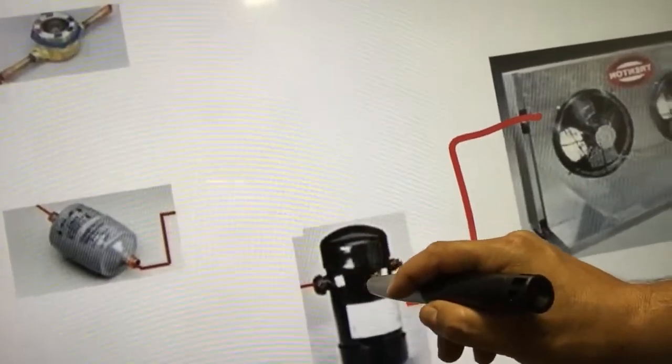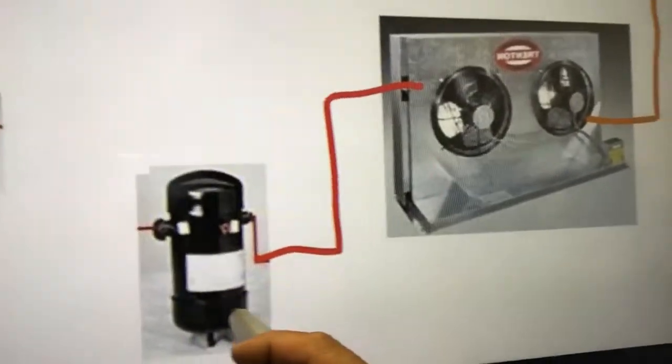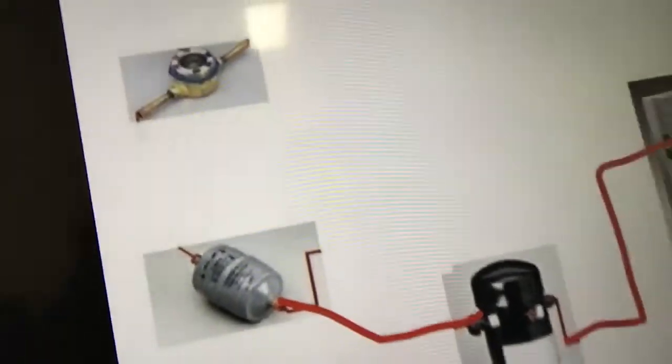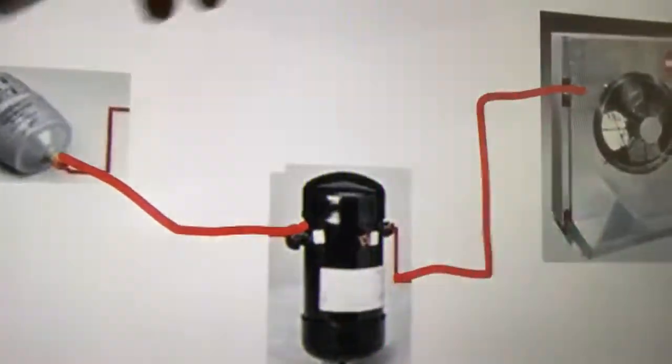From the receiver tank, notice that the refrigerant doesn't undergo any physical change — it stays as high pressure liquid refrigerant. It comes out of the receiver and goes into the filter dryer, where again no physical state change occurs. It keeps going into the sight glass, which just lets you know the refrigerant has no moisture, and then into the TXV.